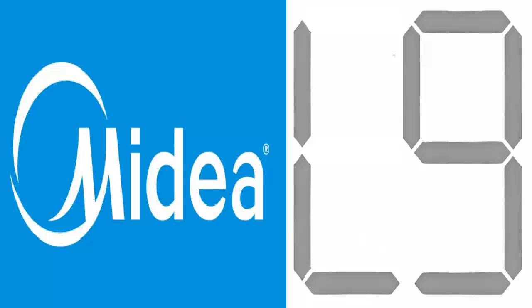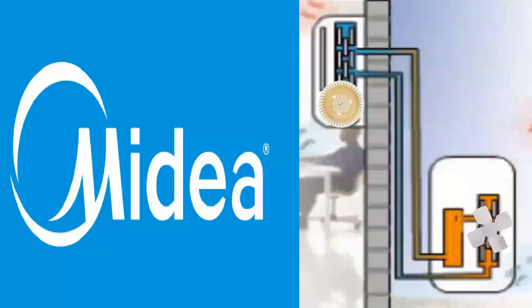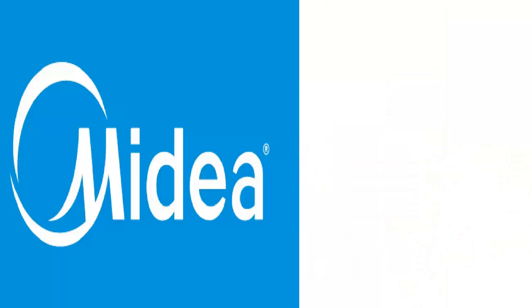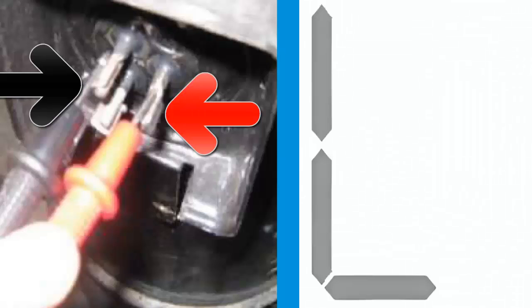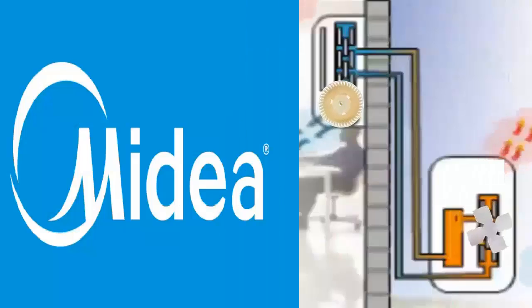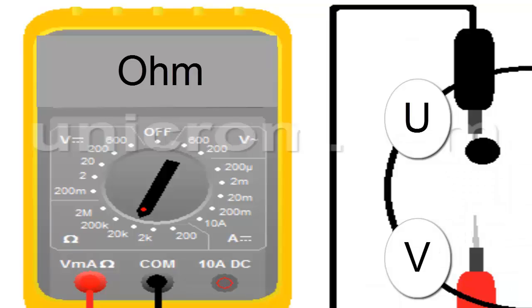For the diagnosis of the above codes, follow these steps. 1. With the equipment powered off, disconnect the compressor and check the condition of the compressor motor by measuring the electrical resistance between the compressor terminals or pins denoted by the letters U, V, and W. The electrical resistance measured between pairs of pins should be nearly equal and be between 0.9 and 5 ohms.